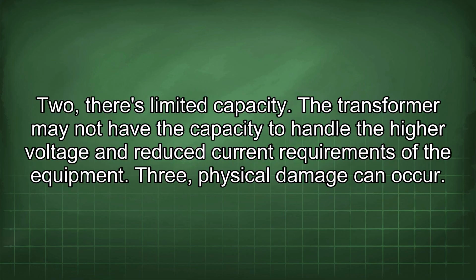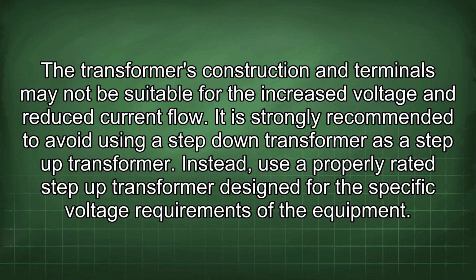2. There is limited capacity. The transformer may not have the capacity to handle the higher voltage and reduced current requirements of the equipment. 3. Physical damage can occur. The transformer's construction and terminals may not be suitable for the increased voltage and reduced current flow. It is strongly recommended to avoid using a step-down transformer as a step-up transformer. Instead, use a properly rated step-up transformer designed for the specific voltage requirements of the equipment.